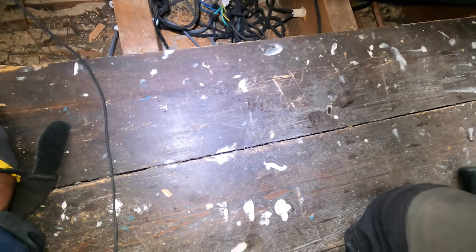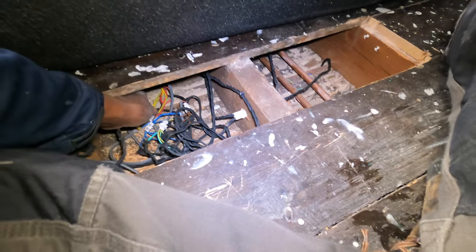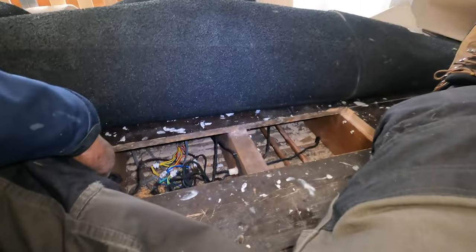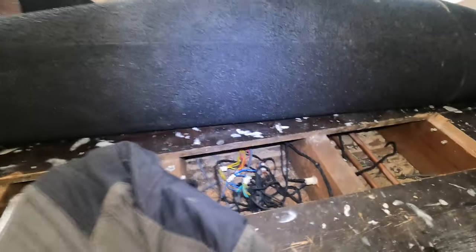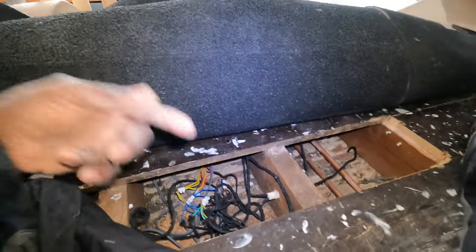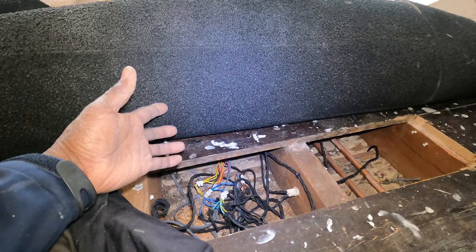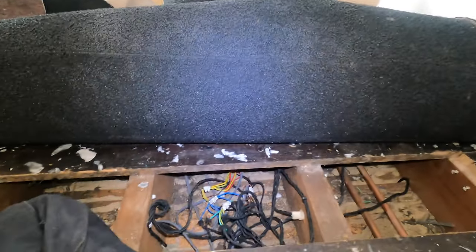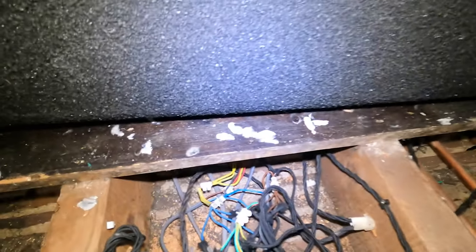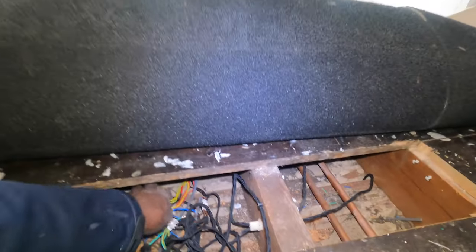There are some massive connections on the rear. Oh my days! So these are the connections on the rear. Mate, I can't just connect — I can't run a cable and connect here. No way. All that needs to be in a proper junction box, in a proper connection. If I'd done that, that would be a terrible thing for me to do as an electrician. I can't do that, mate. And these cables are too short — I can't even get to work on them.